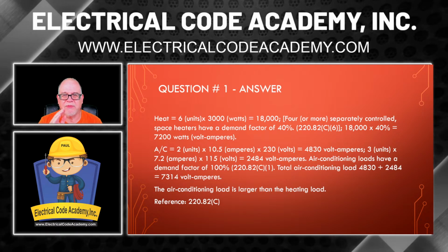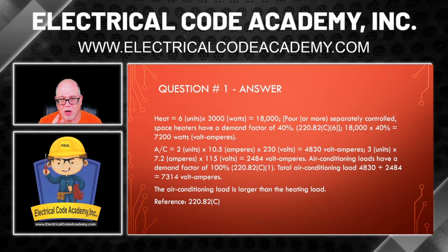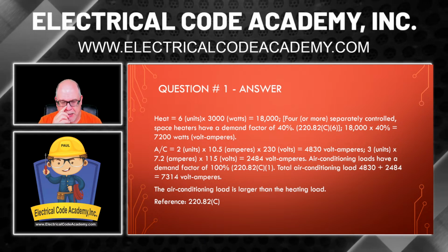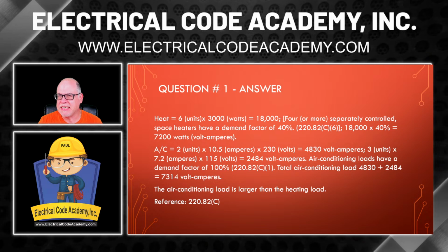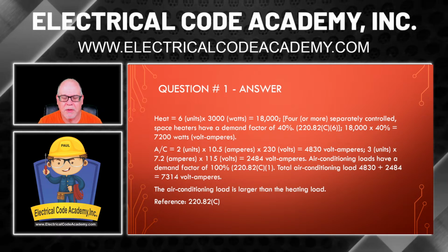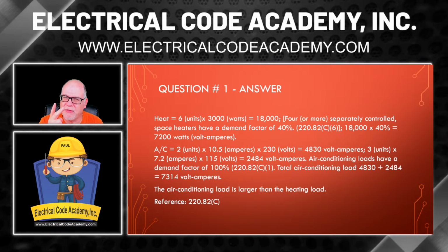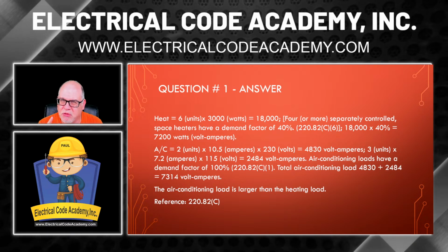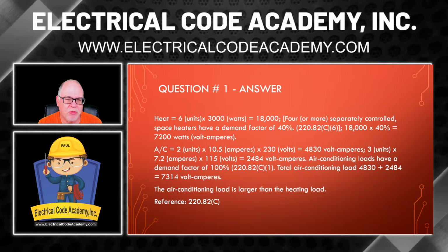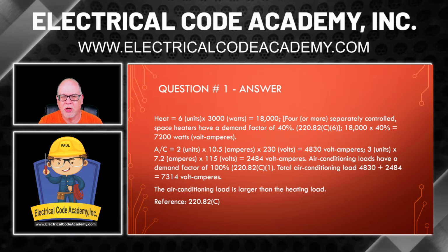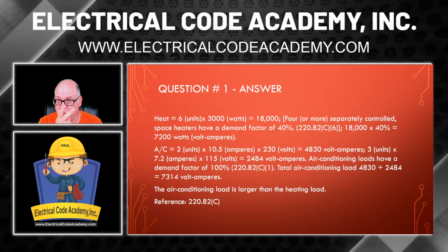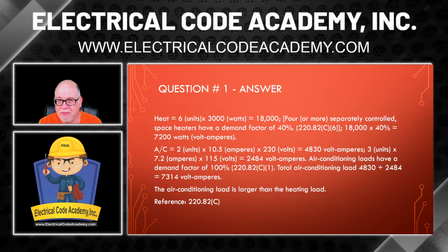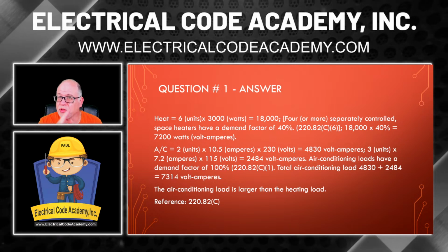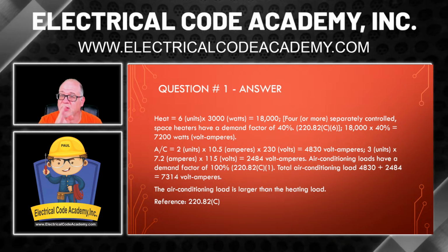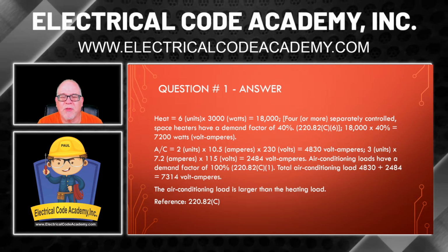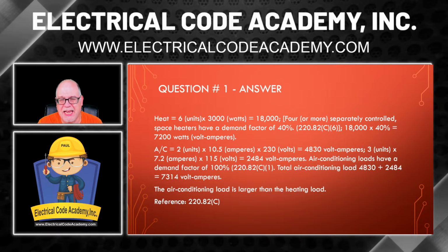Now let's look at that AC, because we know that we've done the heat already, and 7,200 is what we're working with for the heat. Is that going to be greater than the AC? Well, that's what you've got to work out. Remember, we had 2 of them at 10.5 amps each, and we had 3 of them at 7.2 amps. So easy math: 2, because there are 2 of them, times 10.5 times 230 volts. Remember, use the voltage that's given in the question. That's going to give us 4,830 VA.